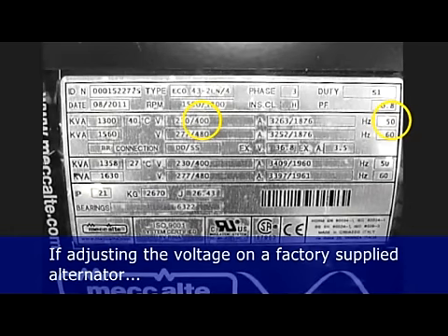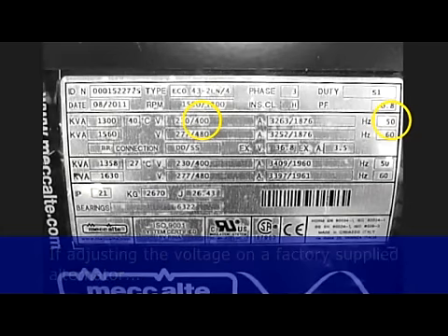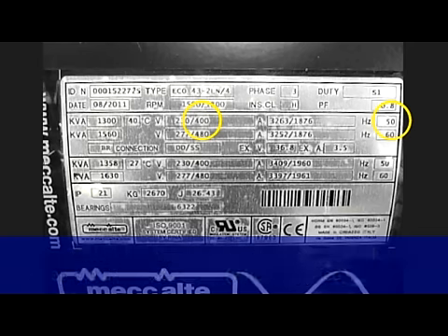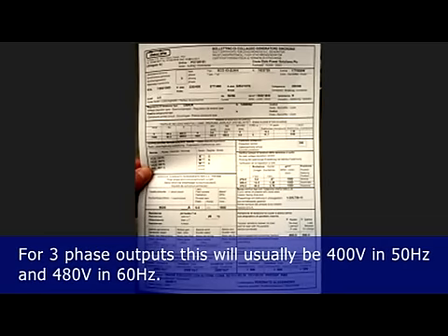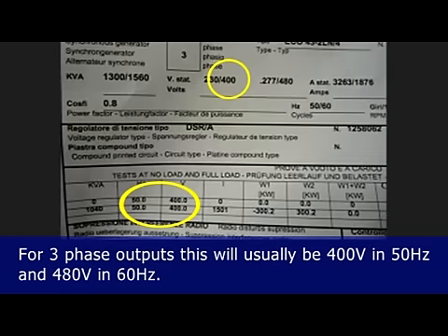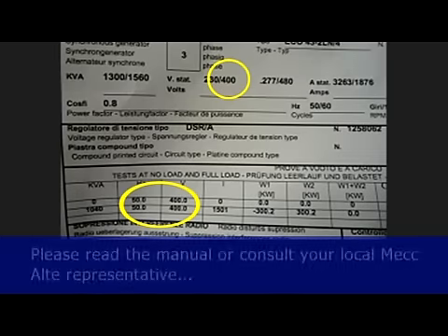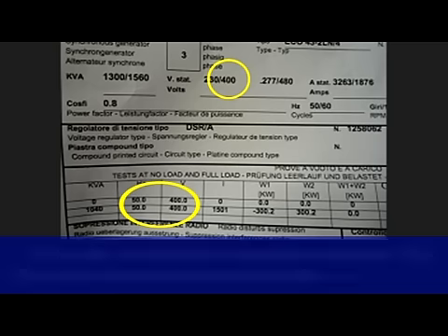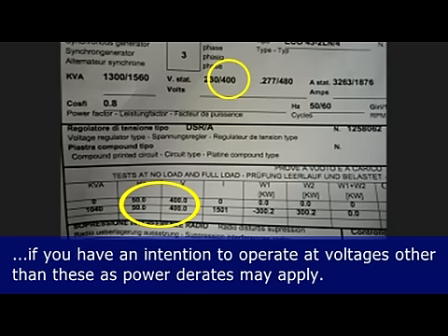If adjusting the voltage on a factory supplied alternator, the voltage will be set to a value indicated on the nameplate and shown on the test report where supplied. For three phase outputs, this will usually be 400 volts at 50 hertz and 480 volts at 60 hertz. Please read the manual or consult your local Mecc Alte representative if you intend to operate at voltages other than these, as power de-rates may apply.